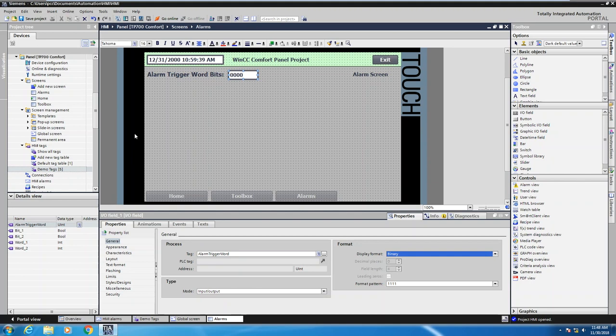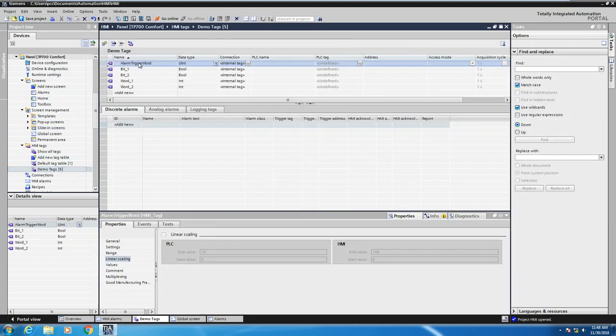Now I'm going to move over into my project tree under the HMI and open up my demo tags tag table. This is where my alarm trigger word is located. I'm going to highlight this alarm, and then in the middle window down below there is a discrete alarms tab — this is where you add in the individual alarms. The benefit of adding alarms right at the tag level is that the tag will automatically be selected for you.